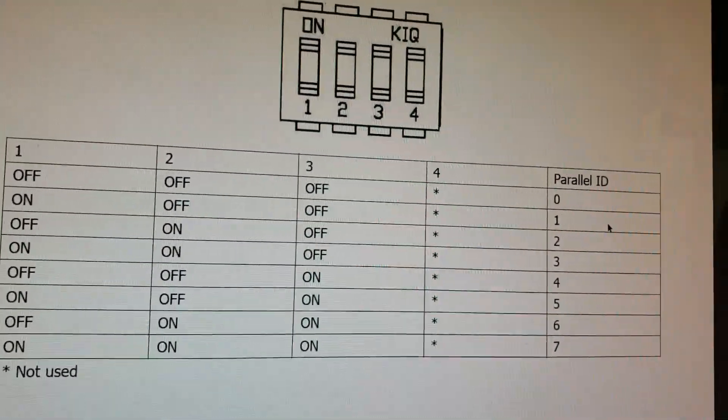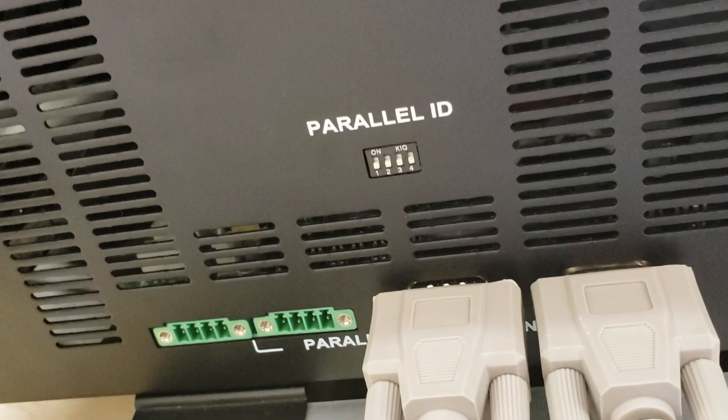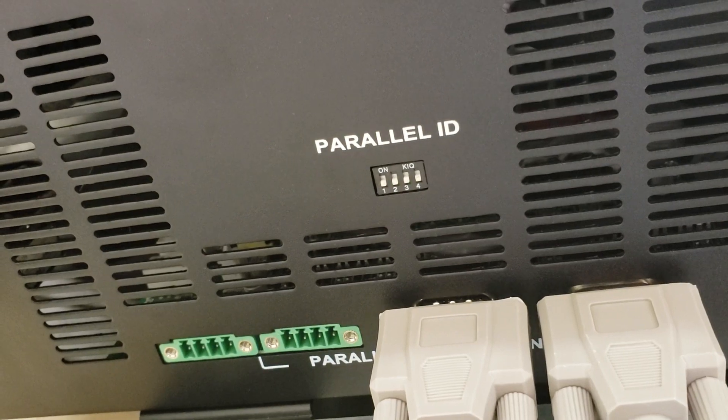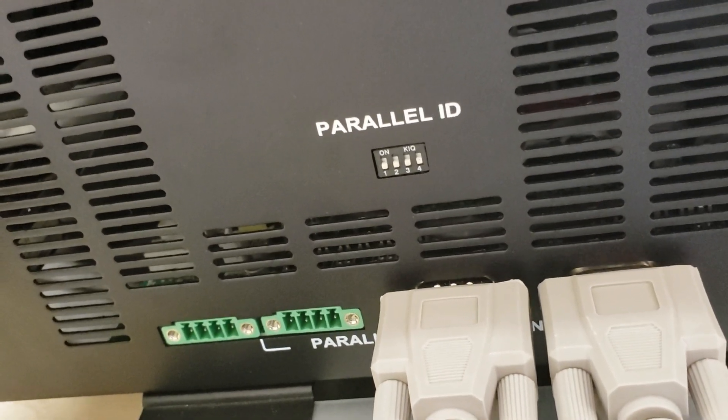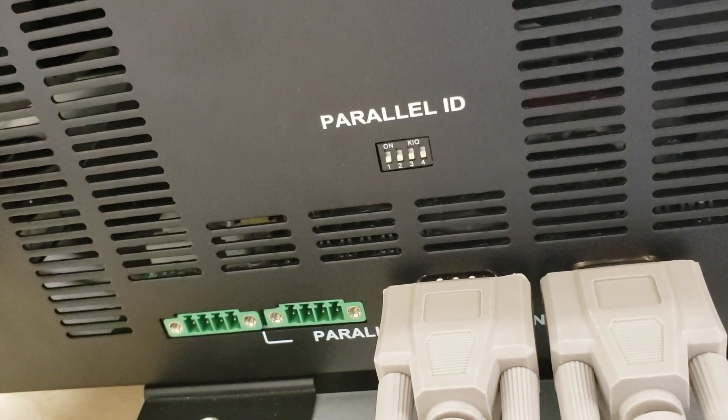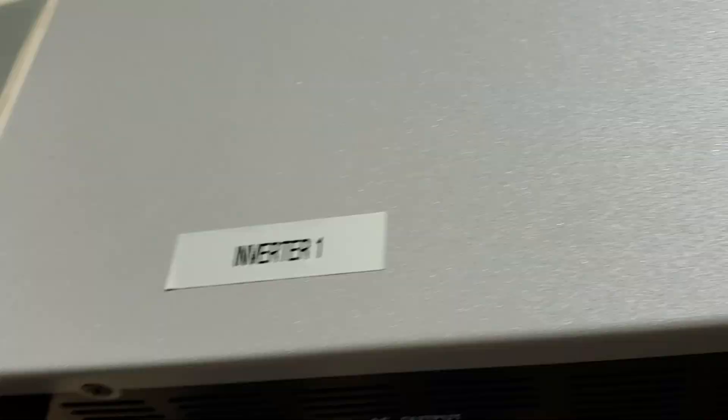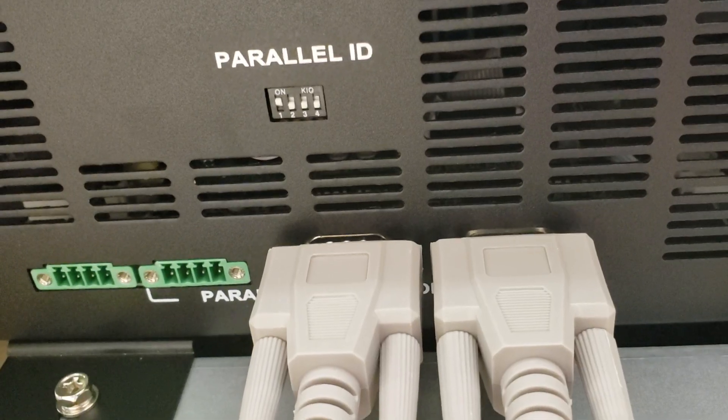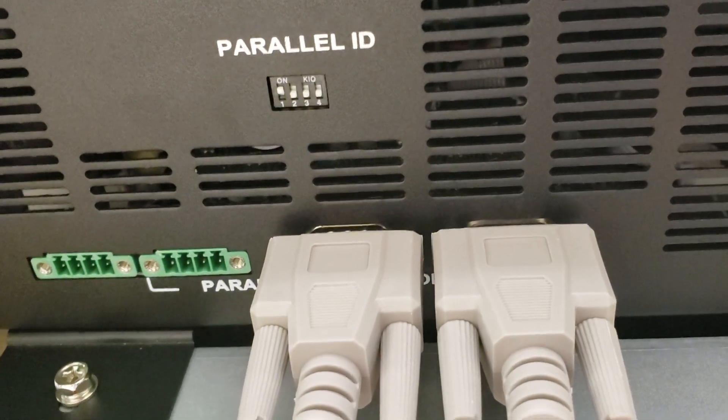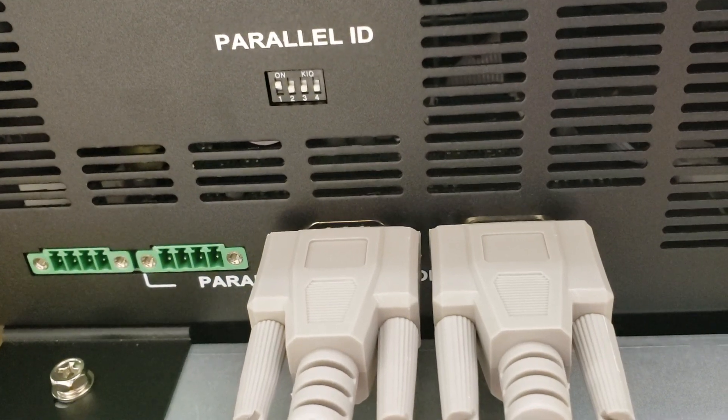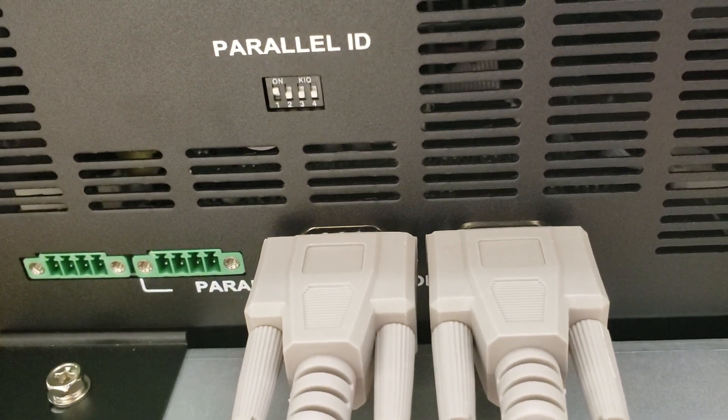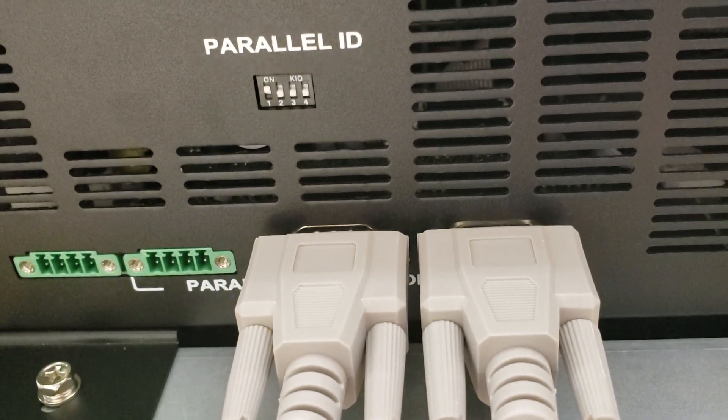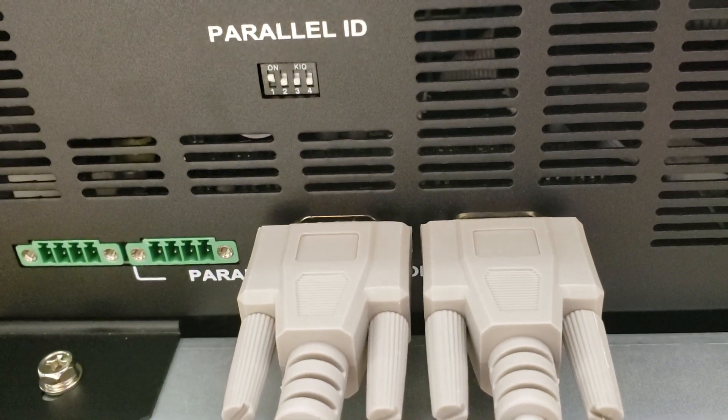Now let's take a look and see how that works on the inverters themselves. Here's the parallel ID setup for inverter number one. As you can see, all four of them are in the off position as shown on the diagram in the owner's manual. This is inverter number two, and only one switch is in the on position as prescribed in the owner's manual for parallel ID one. One is on, two and three are off, and of course four is not used and it's left in the off position.